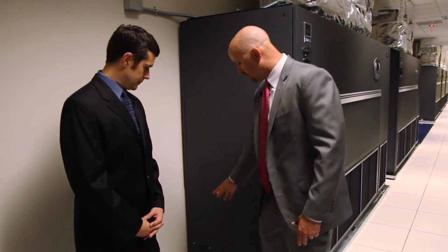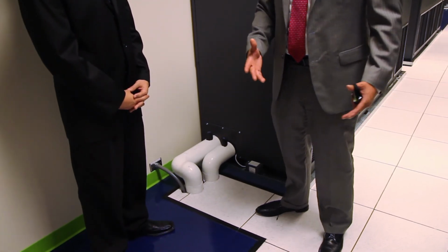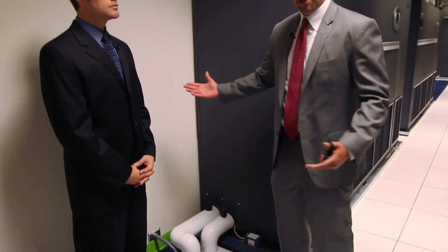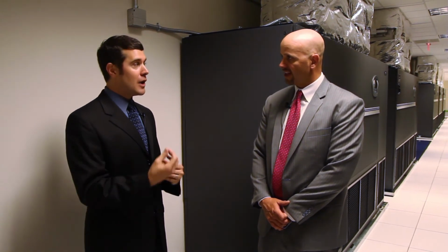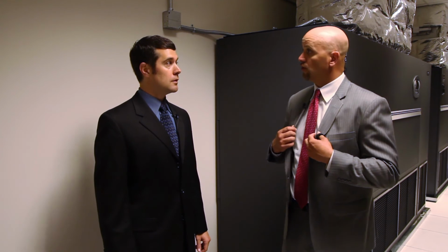First off, here again, redundancy. We're standing on a suspended floor, and all the water that these units use is piped underground, so in case there's a flood or a malfunction, it's below the racks. For the most effective use of space and the ability to scale, they put air handlers in here instead of air conditioning units, because the room required to have all that is not practical, never mind the operational hazards it might bring up. I don't know what the temperature is in here, I guess I could look, but it's very, very cool.